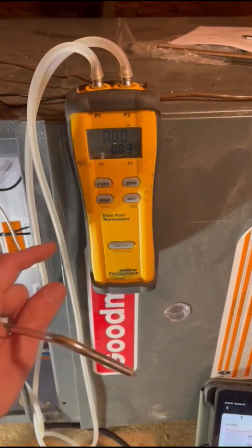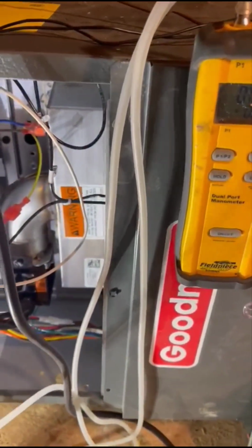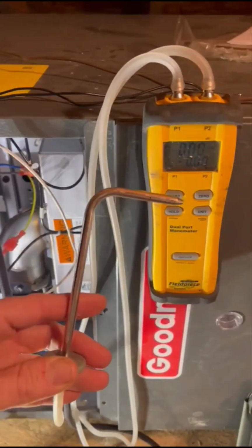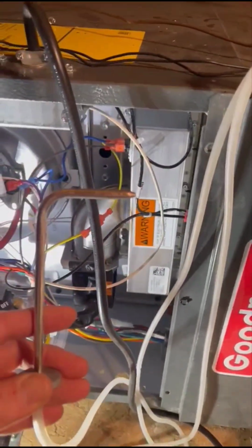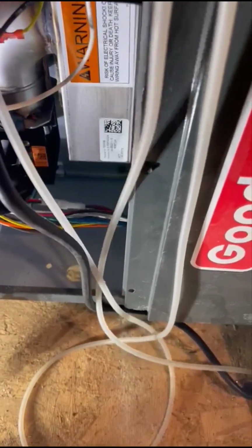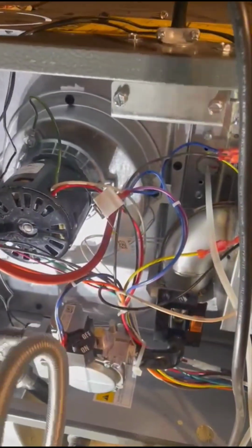Okay, next thing is zeroing out our manometer. 0, and always the pitot tube needs to sit against the airflow, so the airflow hits the tip of it. That's how it measures our static. So I remove the high limit switch. Arrow is facing over there. Make sure the high limit is not touching any pieces of metal so it doesn't pop our fuse.